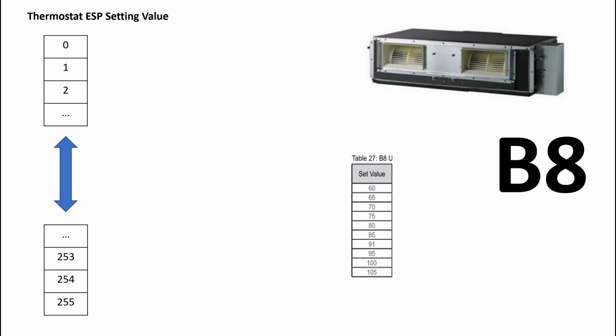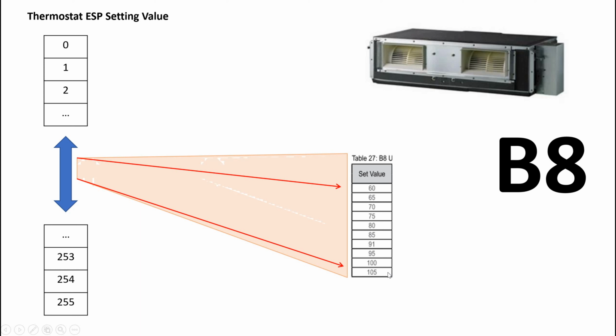From the factory, all thermostats are set by default on 0. Same as ducted type IDU units. When they come from the factory, they are all set for maximum ESP. Let's say if we set the value on 60, it will be the lowest possible ESP setting for a B8 type unit. When we set the value on 105, it means that this is the highest possible ESP setting for a B8 type unit. Let's say we set value 106. It is still the maximum possible ESP setting for a B8 type unit. No difference from setting a value of 105. Same would be all other setting values up to 255. If the value is set to 59, it's still the maximum ESP setting for this unit. And it will be the highest ESP for all values set from 0 to 59.